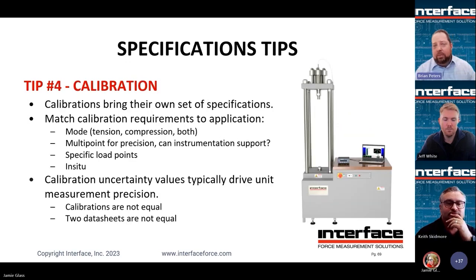Calibration. We could do a whole other webinar on calibration, but for best performance and best match, you want to try to ensure your calibration is as close to what your actual test is going to be. So do you have tension or compression data? Do you need both? Do you only need one? Like we talked about several times, can you run a multi-point cal instead of just a single full-scale value? And that's true for the sensor.